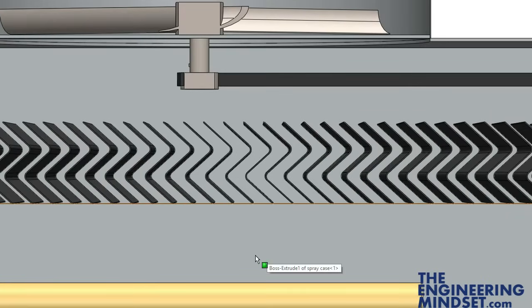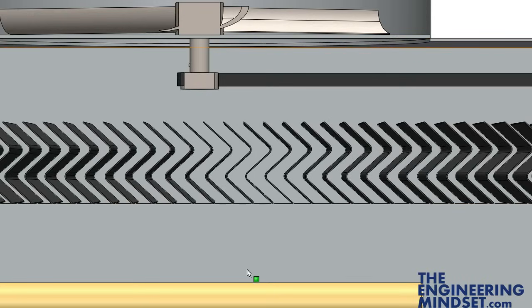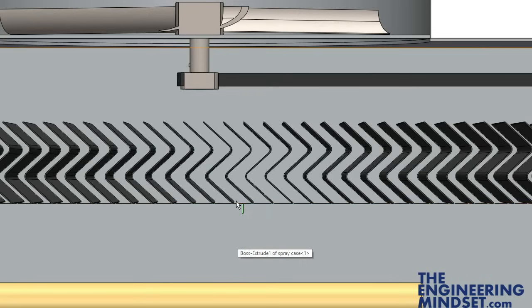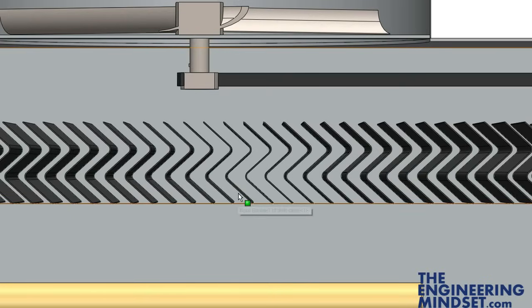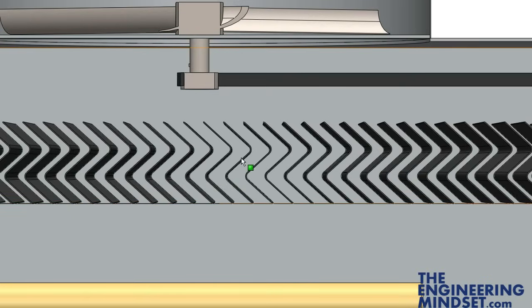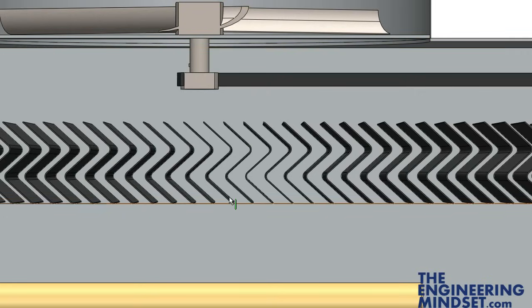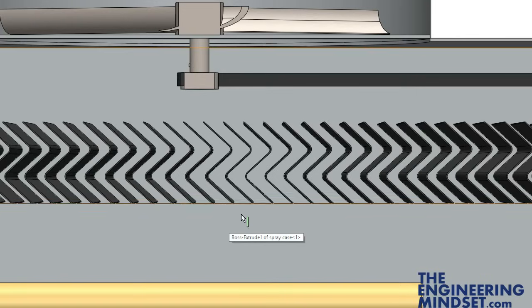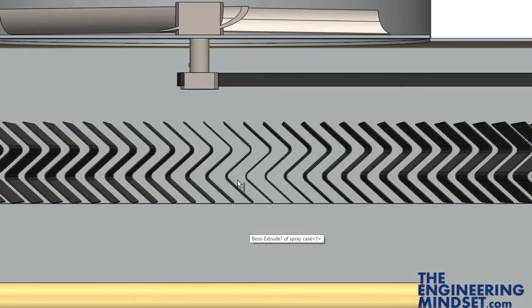What happens is the air enters into here. It's being pulled by this fan at the top here. The air is coming in at a high velocity and it's impacting, hitting against the surfaces. It's going to make these really sharp turns to get out of the system and get to where the fan is trying to pull it out through. So as it does this and it's colliding with the sides, that's giving the moisture in the air a chance to condense on the sides and then run down.